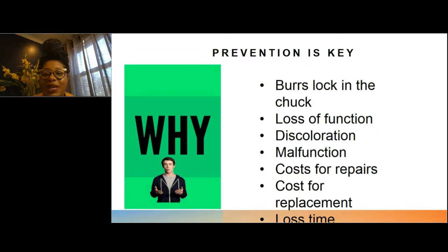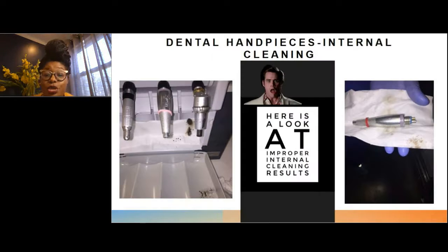So don't be alarmed. It's very important for us to really take a look at our processes. This next slide shows hand pieces where the internal mechanisms were not being properly cleaned. And so through cycles and cycles and cycles of reprocessing, there was a buildup of a lot of things inside of the hand pieces, which were not making the hand pieces work as effectively as they could. A change that was made within our reprocessing, our SPD, is that a whole different machine was purchased in order for us to be able to clean the inner workings.